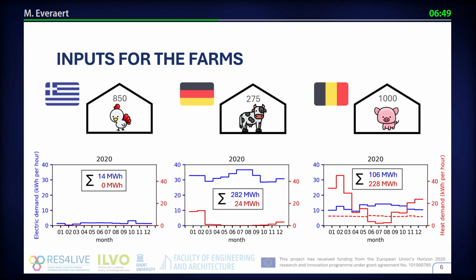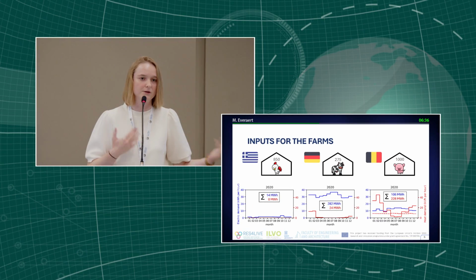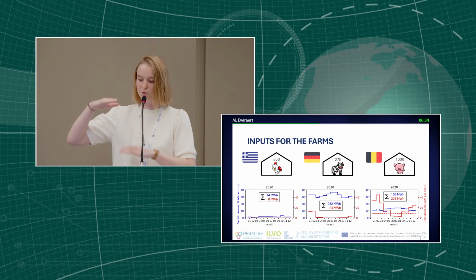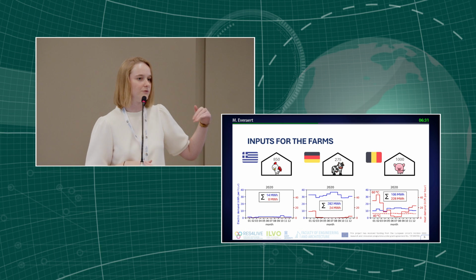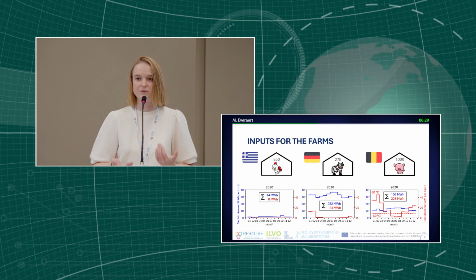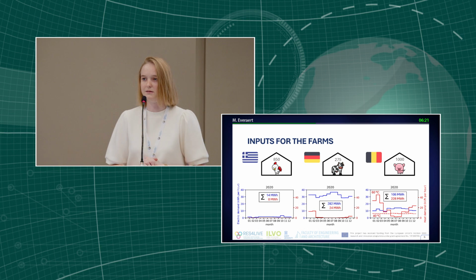Then for Belgium, we actually have a high heat demand because it's quite cold, and piglets need a lot of heat—about 38 degrees centigrade, as most of you probably will know. But there we had a special case, since it's close to our research facility, we have a dual heat demand: a heat demand at 40 degrees centigrade providing underfloor heating, and a high temperature heat demand providing sanitary hot water and heat for the air preheaters. So this barn has actually the highest heat demand.